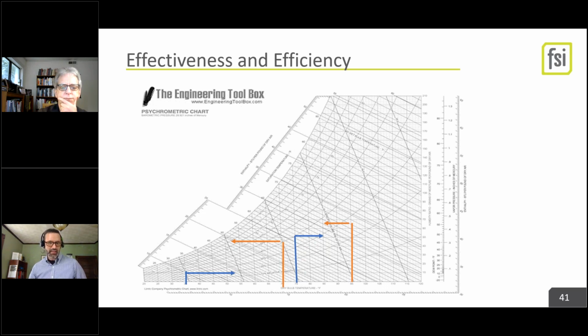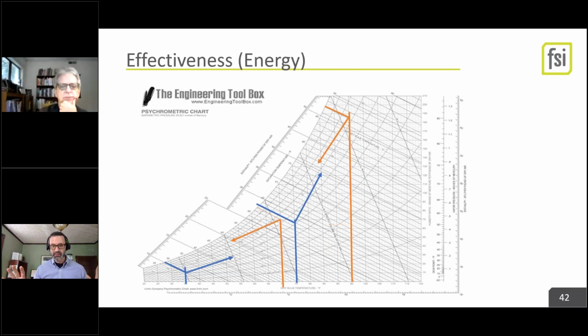So effectiveness is the temperature delta between the incoming airstream and the outgoing airstream, and tells you how much heat, in this case, or on the next slide, enthalpy, so sensible and latent heat, or heat and humidity is another way to say that, you get. And so for Washington State, it's 50% energy recovery, 60% heat recovery. For Seattle, it's 60% heat recovery and 60% energy recovery. So basically, they leveled it up so that you kind of get the same amount of BTUs either way. And what that really means is that if you have 70 going in one side and 50 coming out the other, you got 20 degrees, you want 60% of it, you're getting air back out that's usable at 62. That's what effectiveness means. It's a pretty simple ratio-based equation.